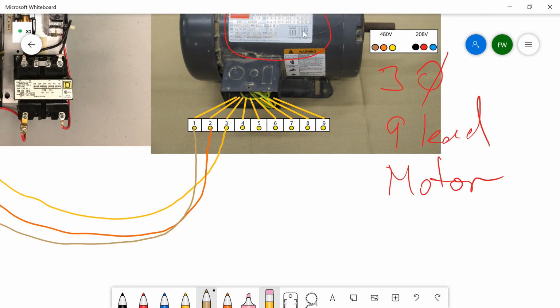So now we have to look at this 9-lead motor. Typically on the nameplate of the motor, it tells you how to hook up the motor for high or low voltage, but if you ever forget, just remember it's a split winding, usually Y connected motor is the most typical. So 1, 2, 3, 4, 5, 6, 7, 8, 9, and then 10, 11, 12 have already been hooked up for you, so you don't have to worry about that. That's why you have 9 leads coming out. If you had 12, then you could hook it up in delta or Y. In this particular case, this is a Y connected motor, so for high voltage, 480 volts, that's what we're hooking it up for. That's what we have coming in.